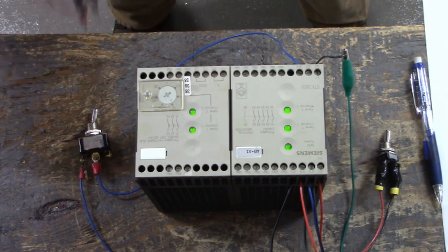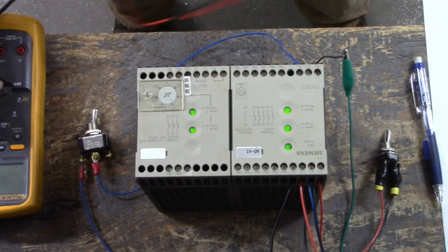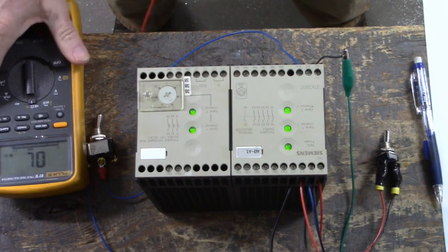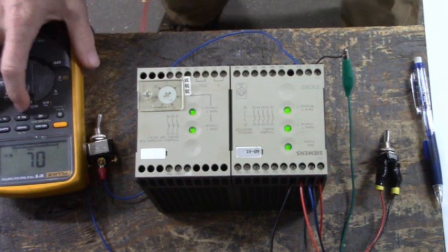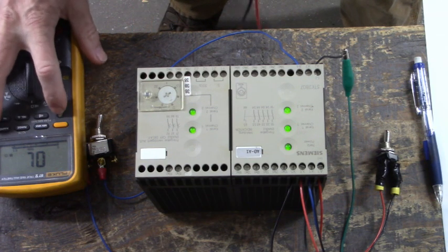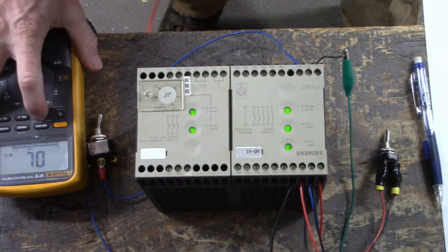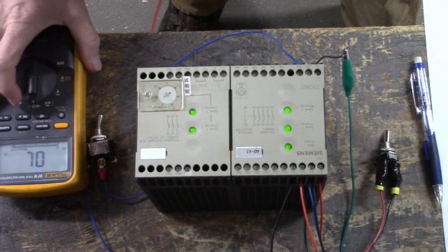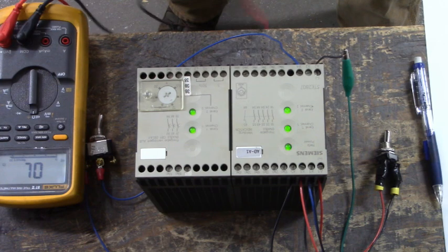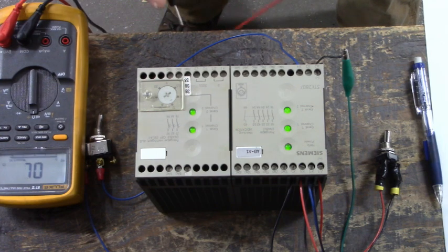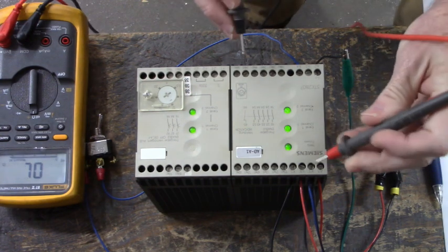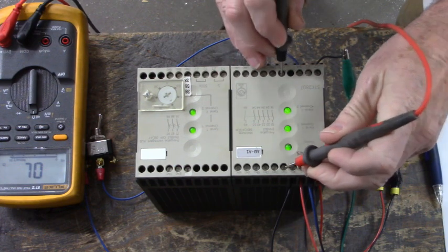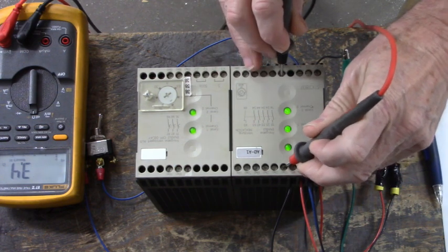With those relays closed, we're going to test continuity. Let me turn that light on. I'll put it in beep mode so you can hear a beep. Now, from 43 to 44, we should have continuity. Yes, we do.